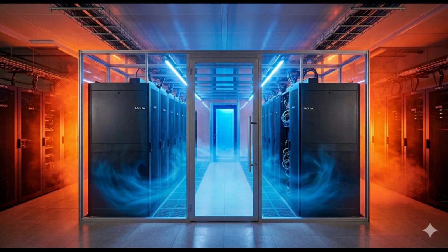A data center isn't a normal commercial building. When you design an office building, your priority is human comfort. When you design a data center, it's an industrial facility. It has one objective, and that is the provision of continuous 24/7 service for critical IT equipment. And humans are actually pretty adaptable to temperature swings. Servers are not. No, they aren't. The operational integrity of millions of dollars of hardware and the data on it relies entirely on two things: continuous power and the continuous removal of thermal energy.